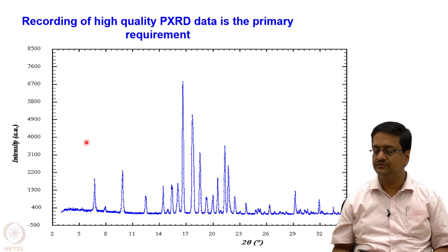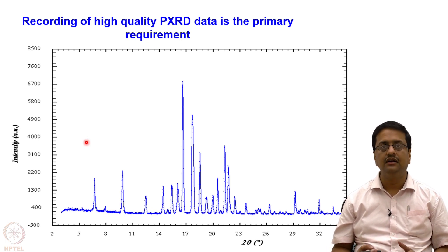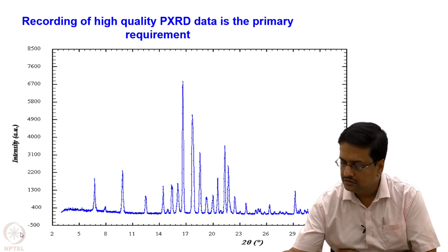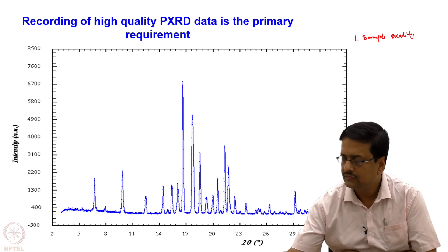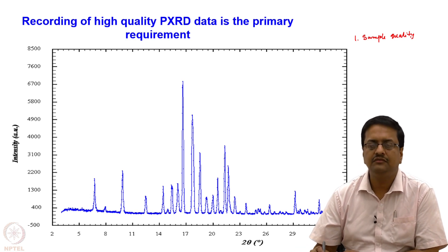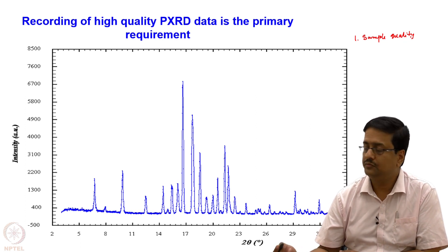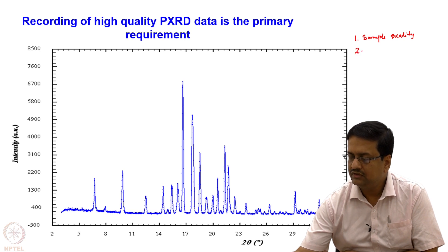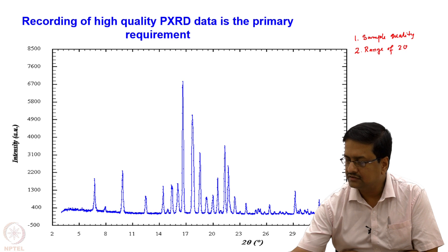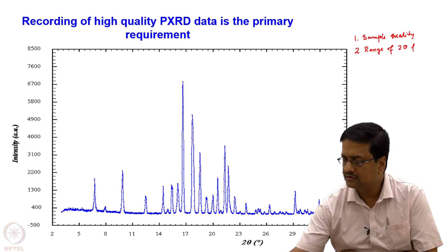The first requirement is to record very high quality PXRD data. For data collection, the sample must be finely powdered, free of moisture, and free-flowing. We also need to know the 2θ range for the sample. Since we do not know this a priori, we can mount the sample and quickly collect data — about 10 degrees per minute — from 3 to 70 degrees 2θ to determine what range of peaks we are getting.